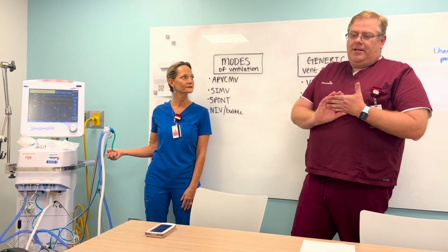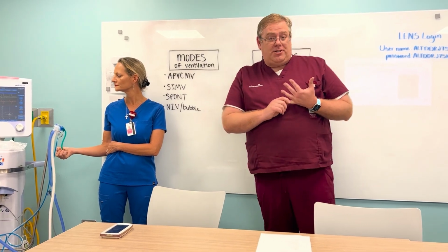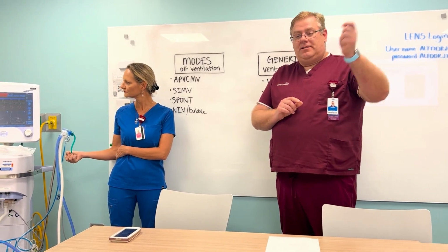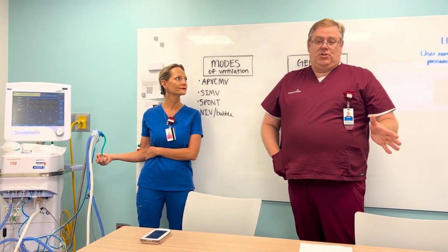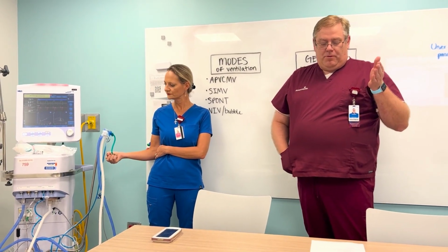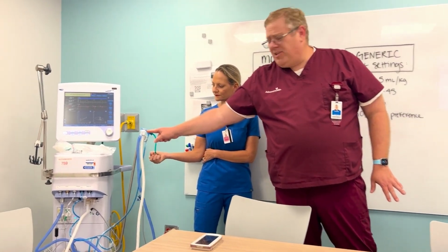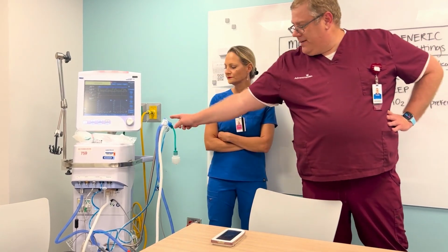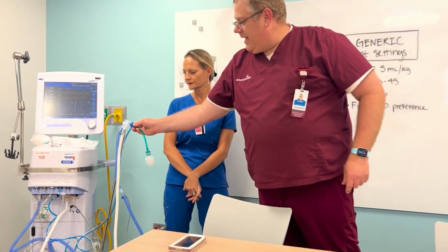So the main things that you're going to see when a ventilator is alarming is that the baby probably needs to be suctioned, which there will be a suction catheter right on the tube and suction the baby with, so down and up. And we'll be going through all of that with training. There might be crud that built up in this part of the tube, just like on the nasal CPAP, where you get water that builds up. We get water that builds up in the flow sensor, and that's a simple solution. Anybody can fix by just disconnecting right here and letting the water drain out.